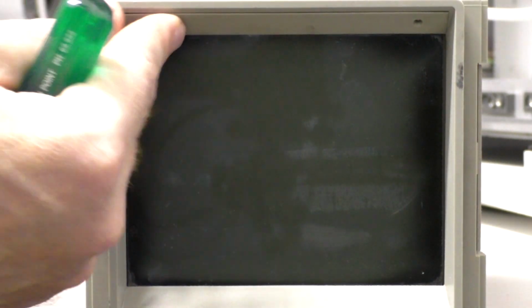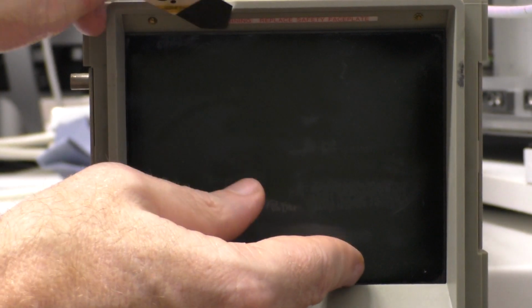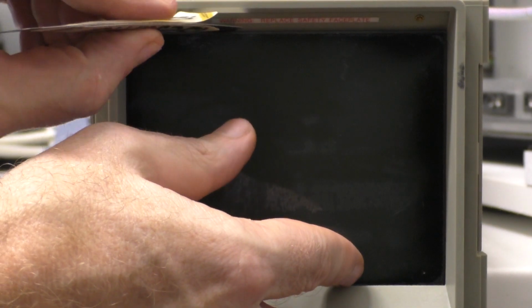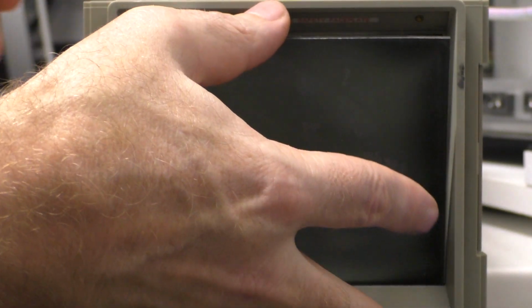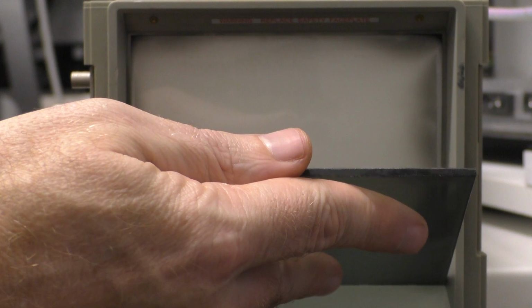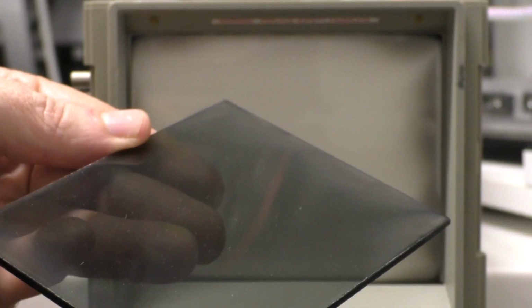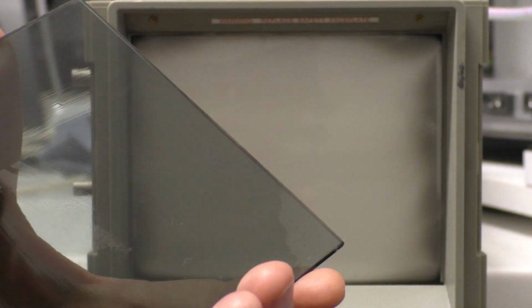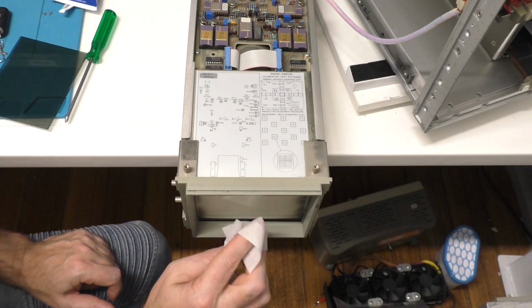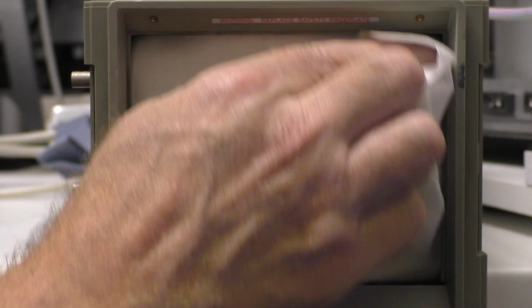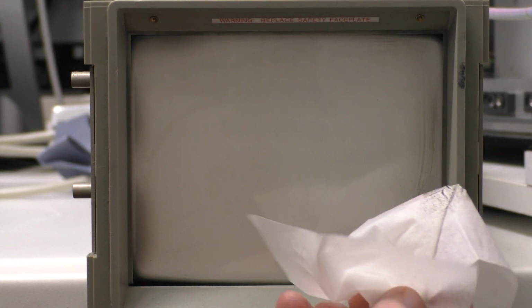Remove the retaining plate. The protective glass cover can now be removed. We can clearly see the buildup of dust on the display and cover. This is the cause of the darkened display. Clean the cover with isopropyl alcohol. Gently clean the display with isopropyl alcohol and lens cleaning tissue.